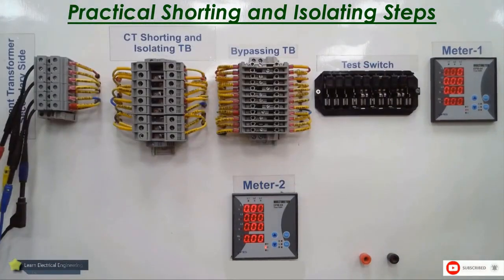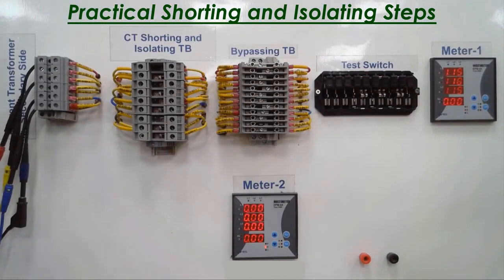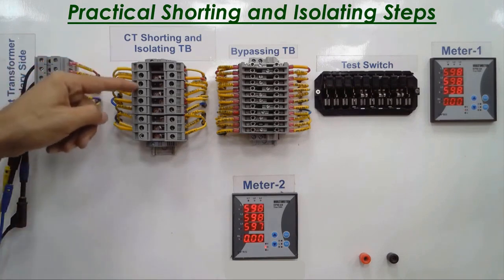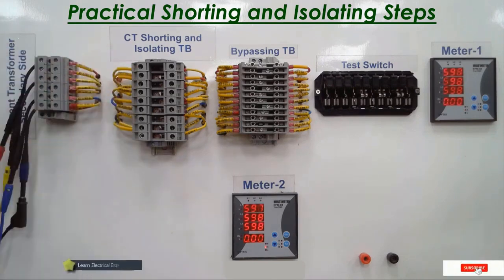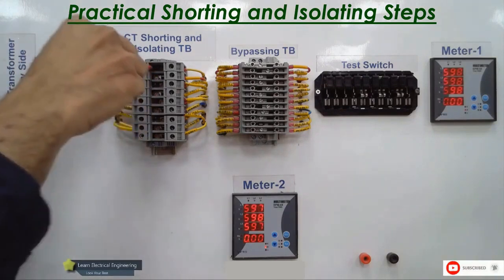I will start injecting my currents. Here, I have set the ratio on the power meters to be 600 to 1. As we can see, the currents are balanced on the 3 phases. It is closed on 3 phases. Very good. As for the shorting process, we agreed that you will do it by first closing 1, 3, 5, and 7, and then opening 2, 4, 6, and 8.